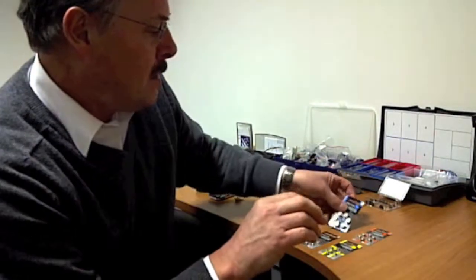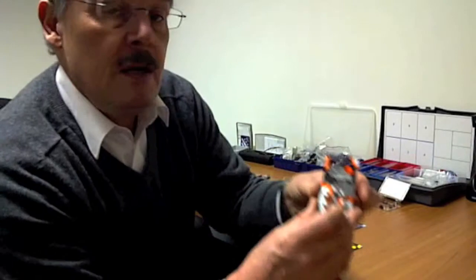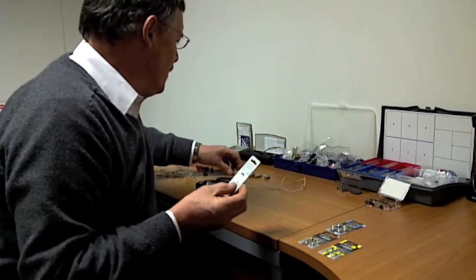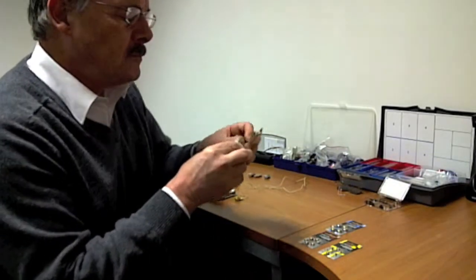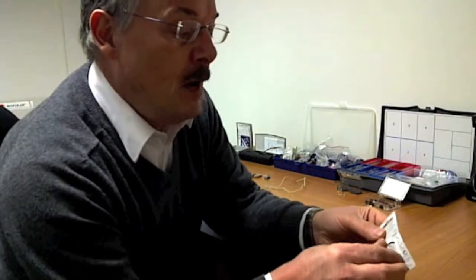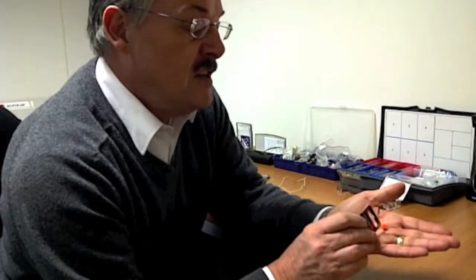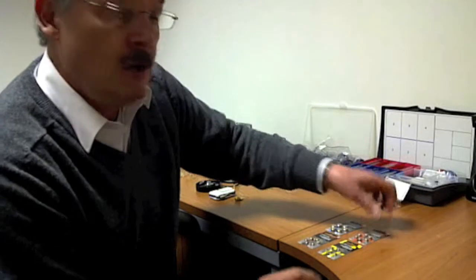So you can see on my hand the battery has a Stay Fresh tab, which you just peel off when you're ready to use. Make sure you do that before you put it in the hearing aid, otherwise it won't work, and then away you go. So the blue battery is the 675. Now the next battery down is the orange battery. This is the 13 battery, and this would typically be used in a number of traditional behind the ear hearing aids for moderate to severe hearing loss. Again, it's in a dial pack, normally 4 or 6. It basically has a Stay Fresh tab that you peel off, and then you pop in your hearing aid and it will fire up and away you go. And most of our modern hearing aids that Ascent Hearing Care provide now have alerting messages in them to tell you when it's going to be time to change your battery.